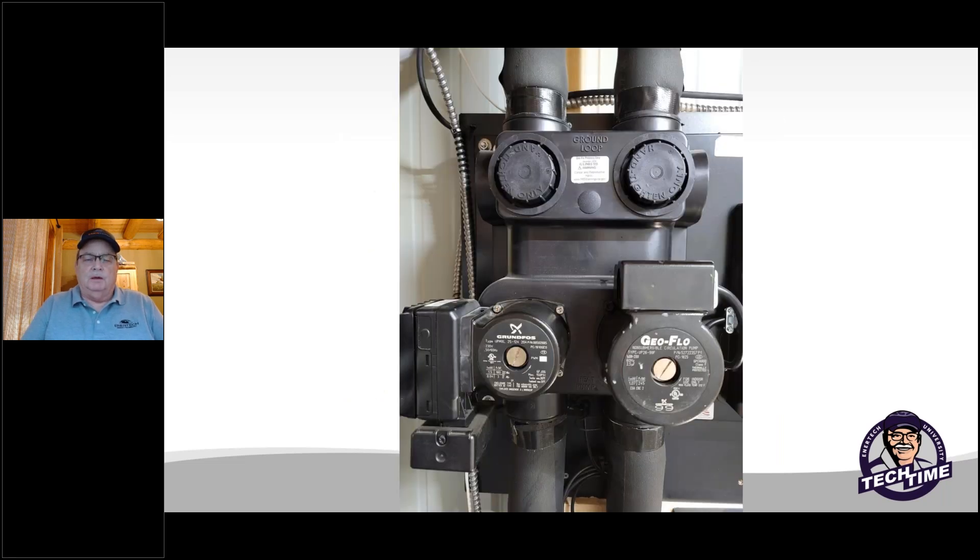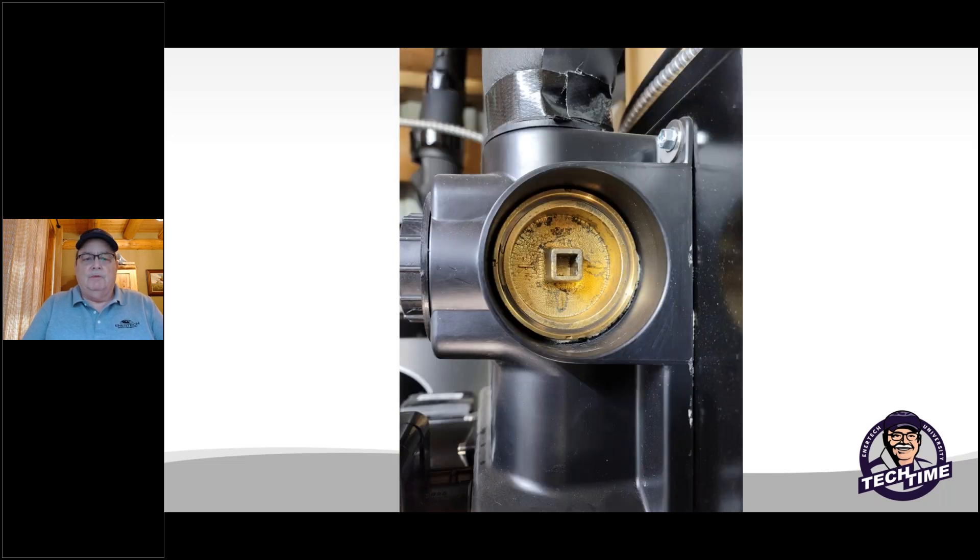So you come upon a flow center that has a bad pump — the Geo-Flo pump on this one right here is bad in this particular case. One thing you need to do is close off and isolate the flow center so we're not draining everything out of the whole loop field. Look at that valve — sometimes it's hard to see the little marks, but a magic marker works wonderfully to show which direction they are. Magic markers are great.